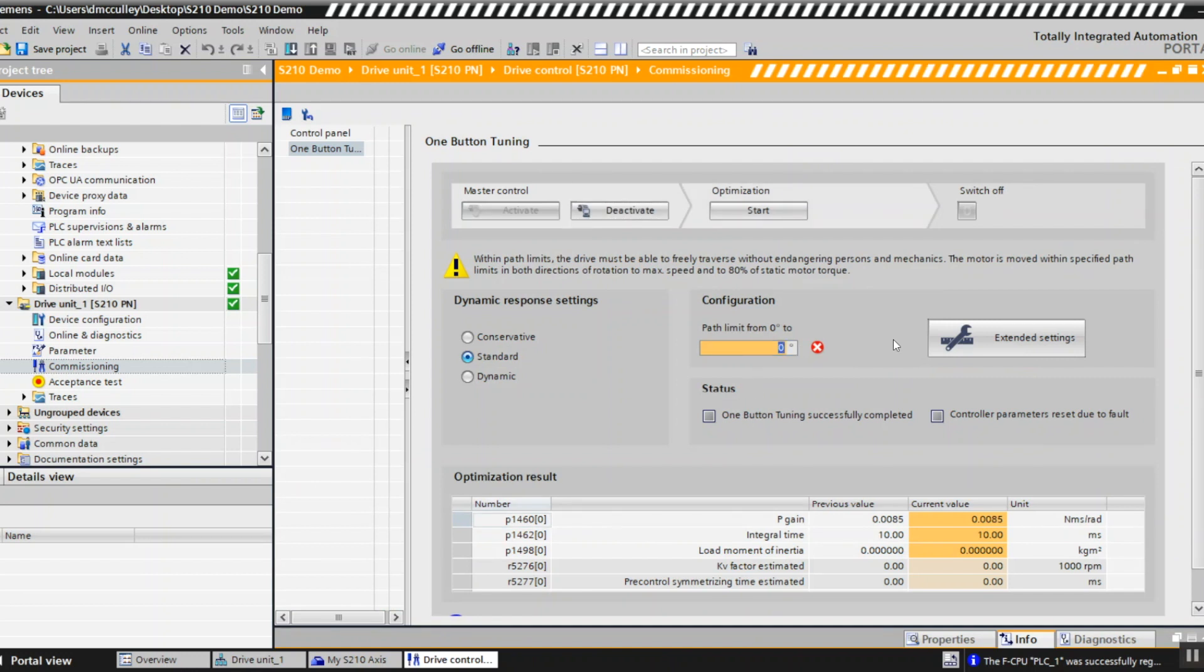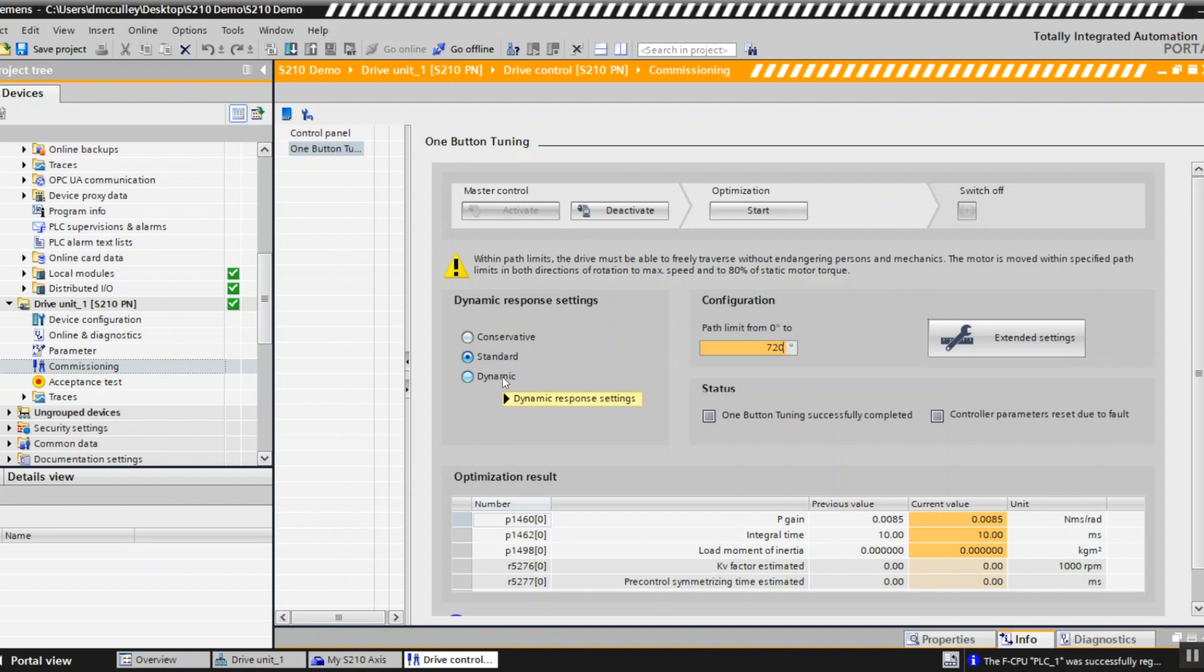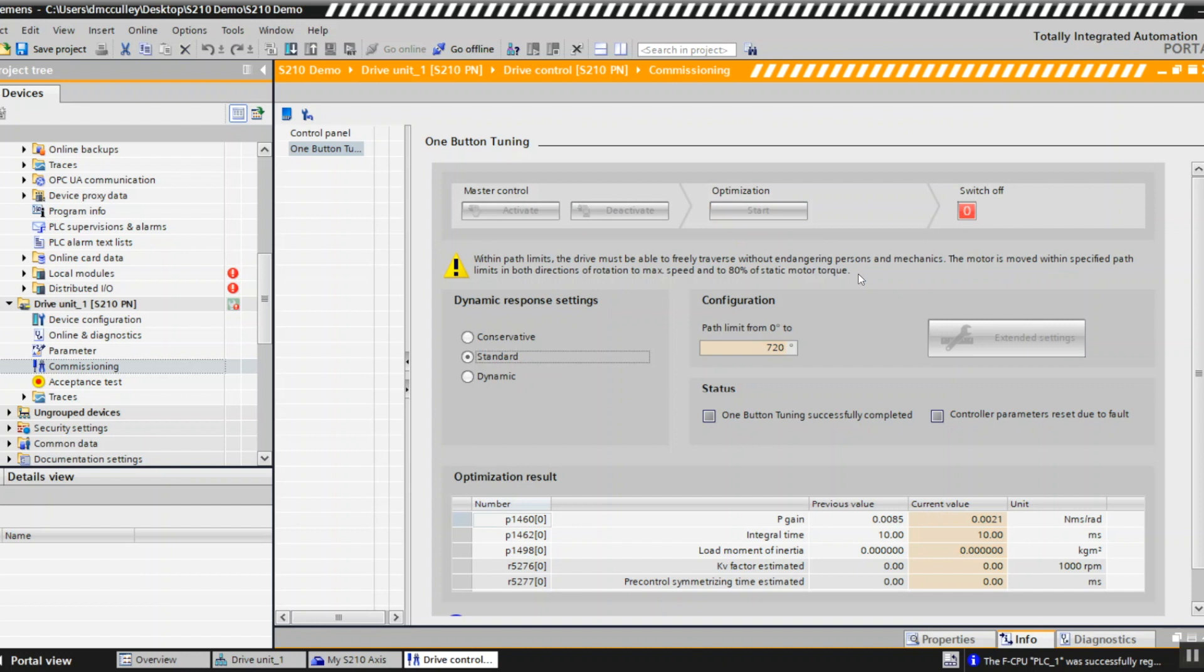I have to set a limit for the distance the drive can rotate. Let's say 720 degrees. I have to choose whether I want to be conservative which would be a soft tuning, standard, or dynamic which would be a stiffer tuning for dynamic applications. I'll leave it at standard, click start and my drive is tuning. It's done tuning and it says one button tuning was successful.